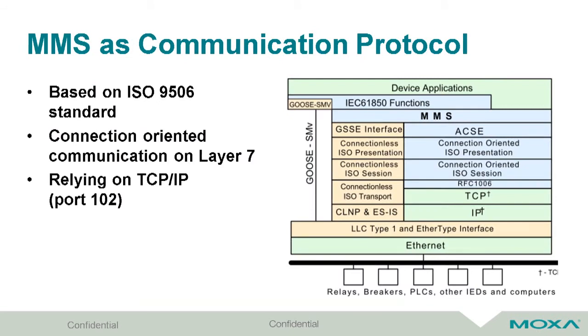We will use MMS, of course, as a communication protocol. So the status of the switch is stored in an MMS server, which will be approached by a client, typically the SCADA system, to either read out what the switch is doing or even to write something in order to configure the switch.